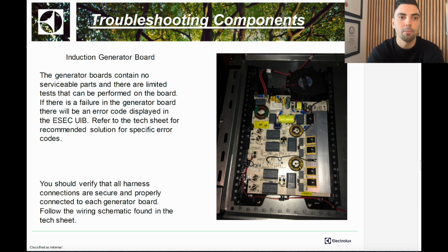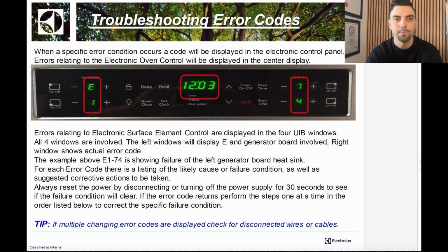The induction generator board. The generator boards contain no serviceable parts, and there are limited tests that can be performed on the board itself. If there's any failure in the generator board, there will be an error code displayed on the ESEC UIB. Refer to the tech sheet for recommended solutions for specific error codes. You should verify that all harness connections are secure and properly connected to each generator board. Follow the wiring schematic found on the tech sheet.